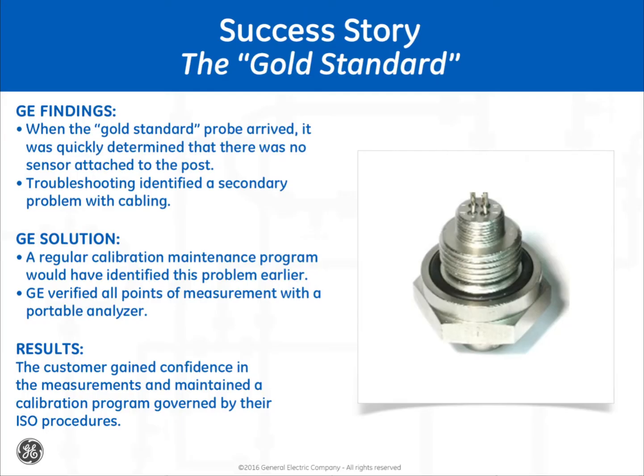When the package arrived, the calibration lab called me down to visually inspect the sensor. I carefully removed the protective shield to find no sensor attached to the posts. After calling the customer and asking him to power on his analyzer, now, of course, with no sensor attached, he was surprised to see that the analyzer was still reading the same it always read.